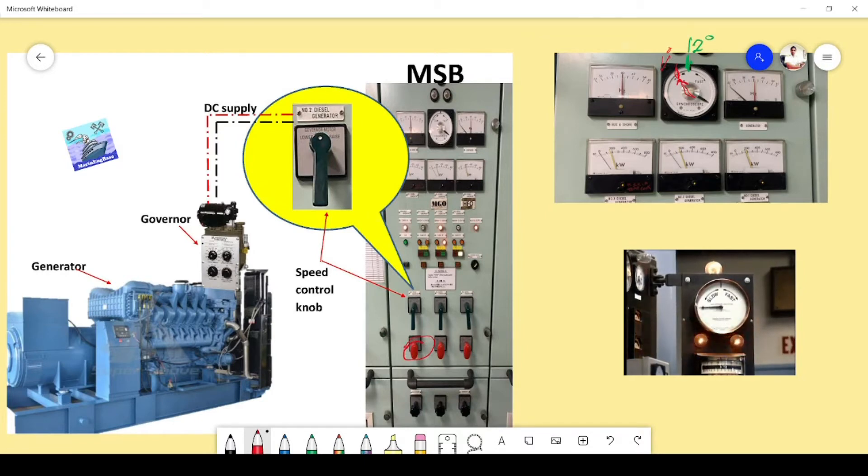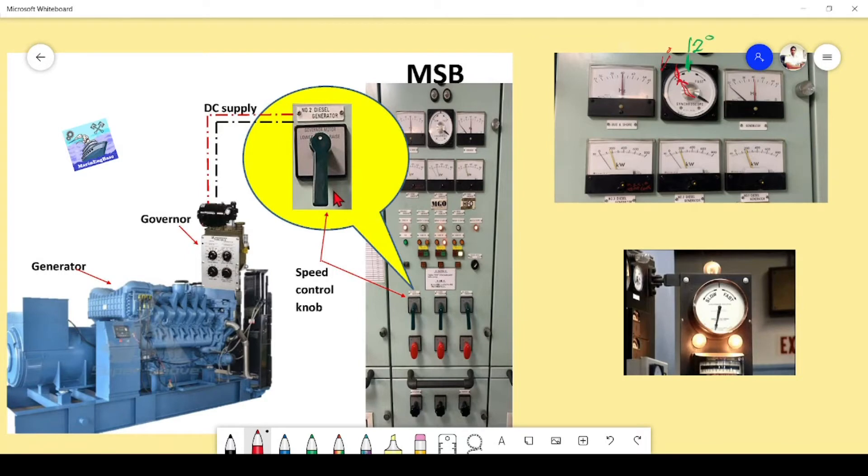The generator will be connected to the bus bar without any difficulty or abnormality. Now I will discuss what these switches are. These three switches are the speed control levers. By rotating these clockwise or anti-clockwise, we can lower or increase the speed of the generator. These red button switches are to close the breaker for generator number one, number two, and number three.